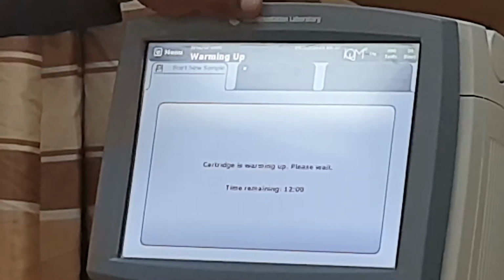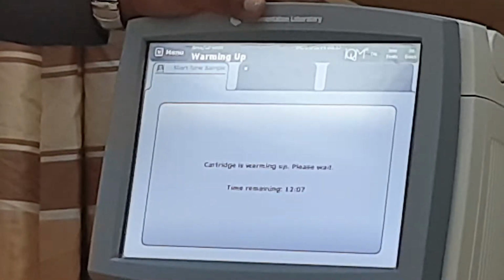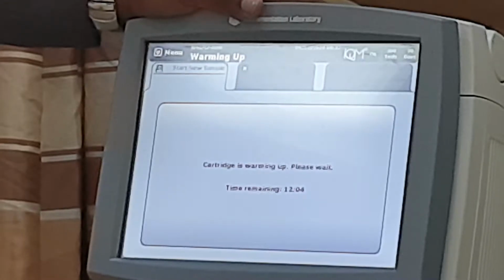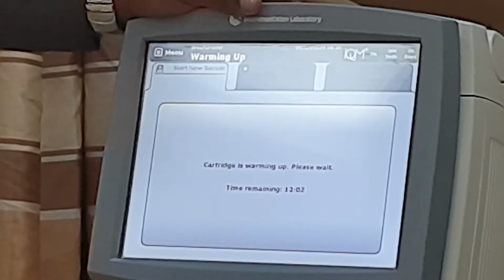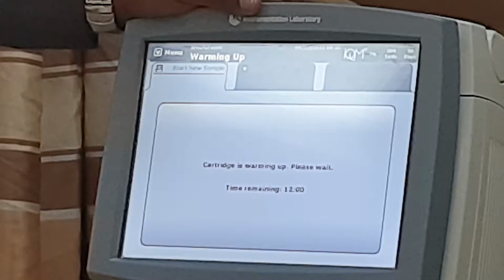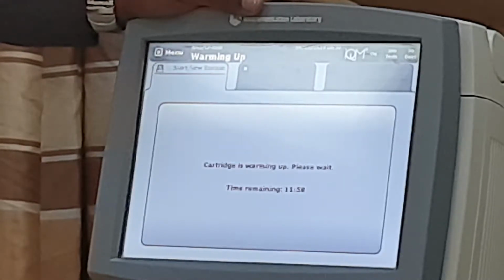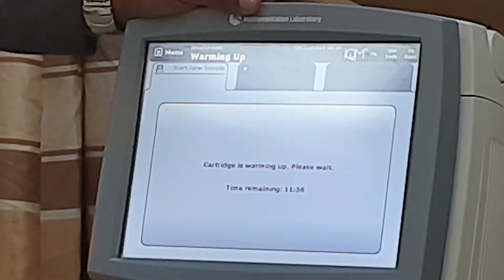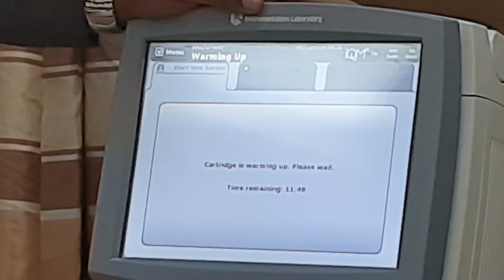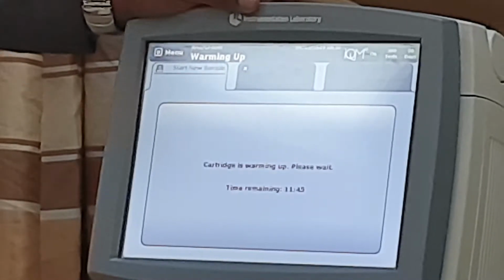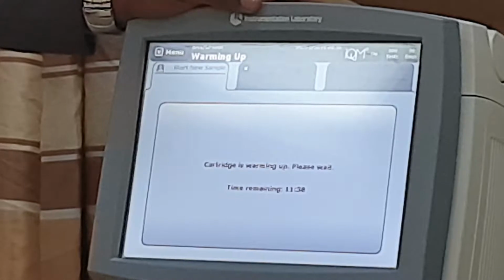4 levels of quality control. We have 4 levels of quality control: A, B, C, and D. For A, every 4 hours the machine will run control as level A. This is the first thing. Secondly, level B: every 30 minutes the machine will run control also, and after every sample, to make sure the machine and all of the parameters are working well.